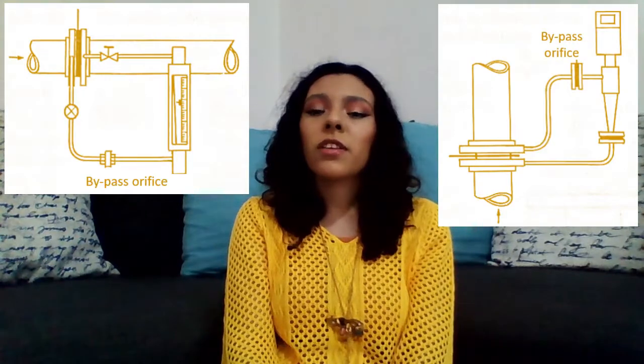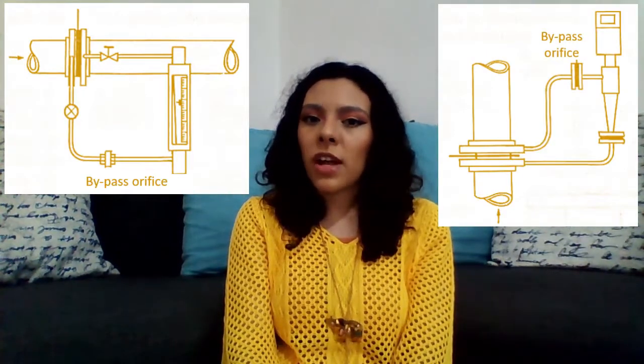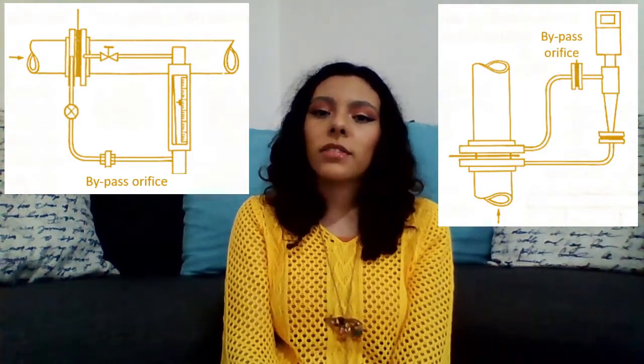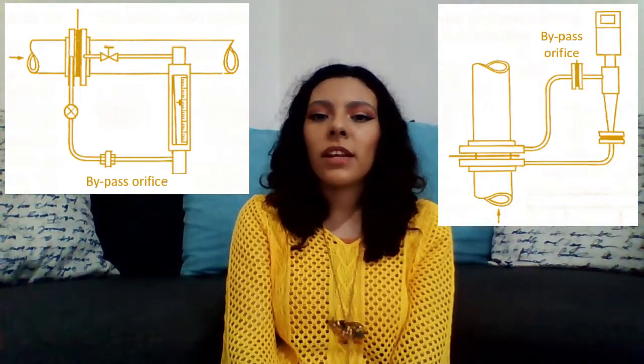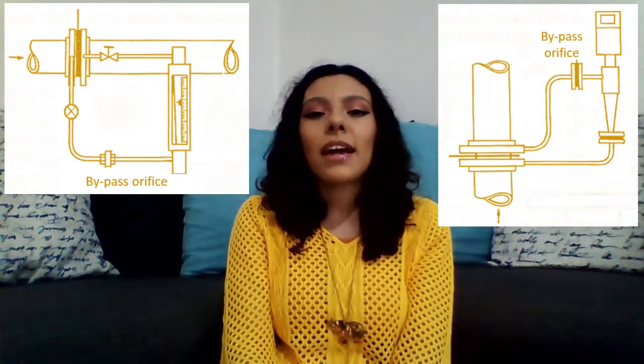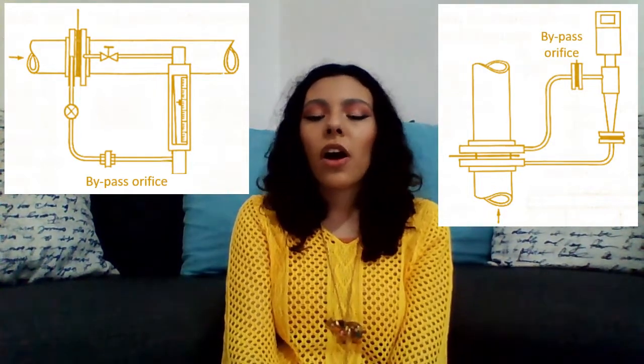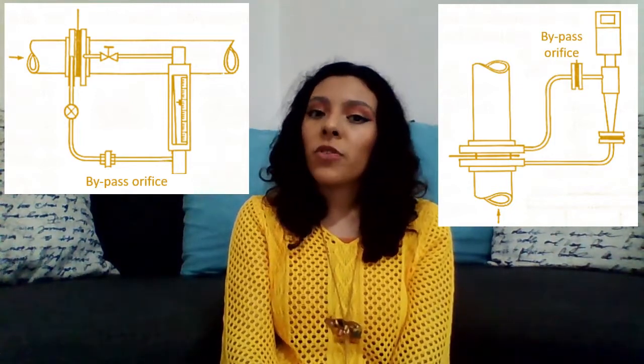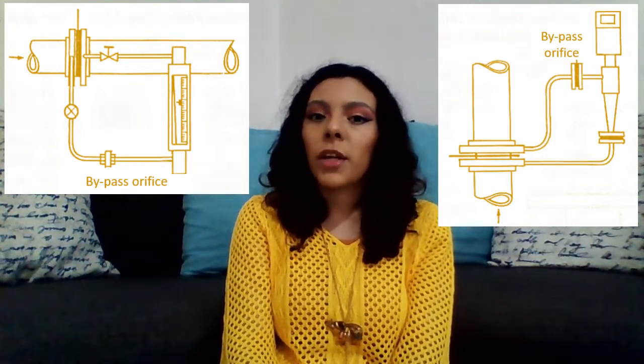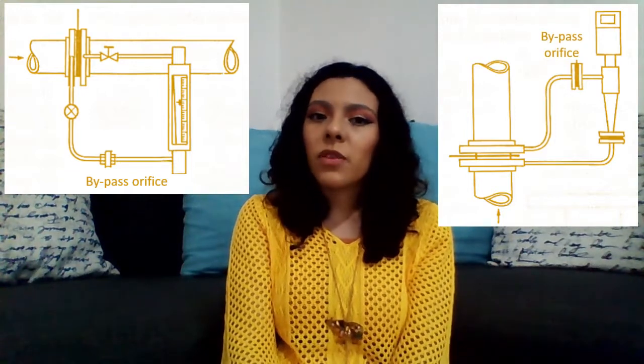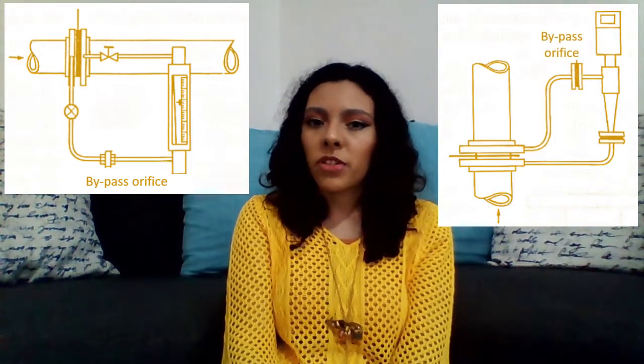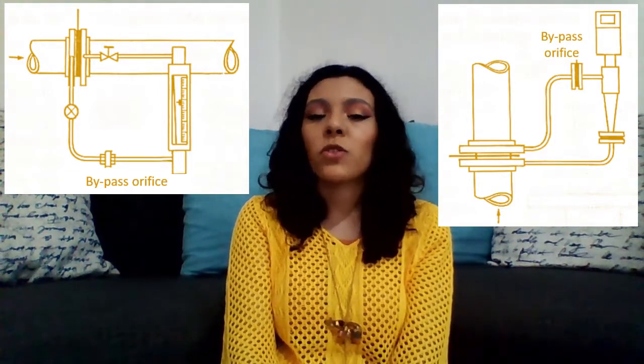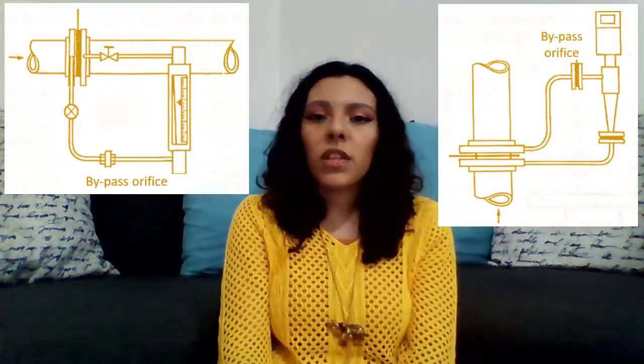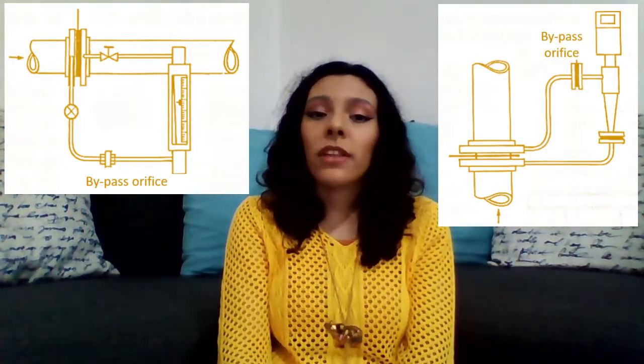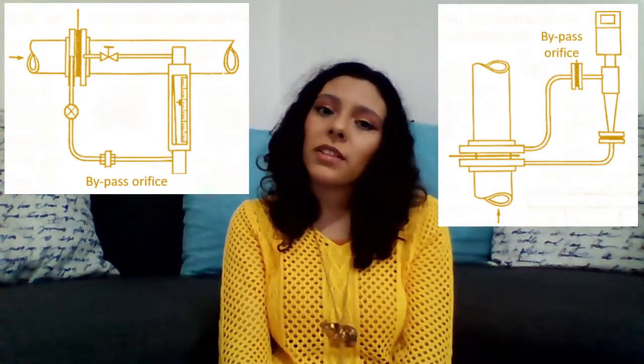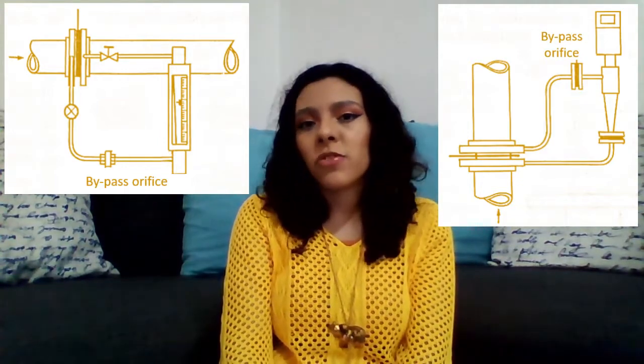The rotameter determines a flow rate linearly proportional to the main flow through the pipeline thanks to a second orifice located in the bypass pipe and calibrated so that the flow marks 100% of the scale when the flow that passes through the orifice plate in the main pipe reaches 100% with the maximum calculated differential pressure. As the bypass rotameter measures flow and not differential pressure, the measurement scale is linear and not square root, as would be expected when using a diaphragm as a measuring instrument.